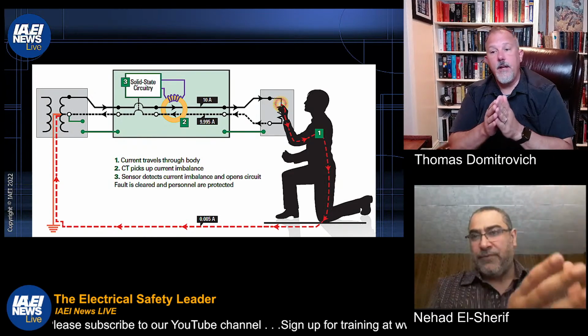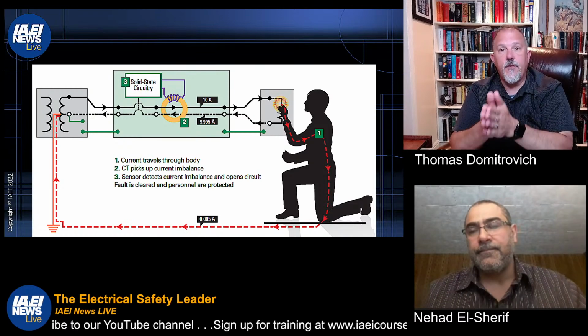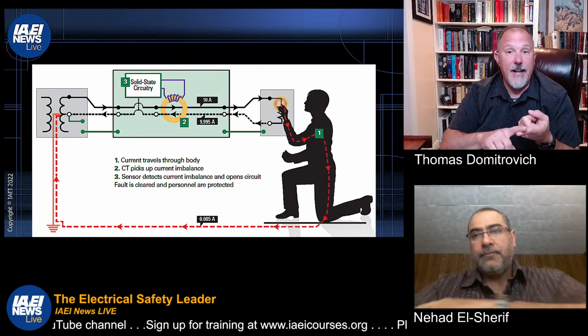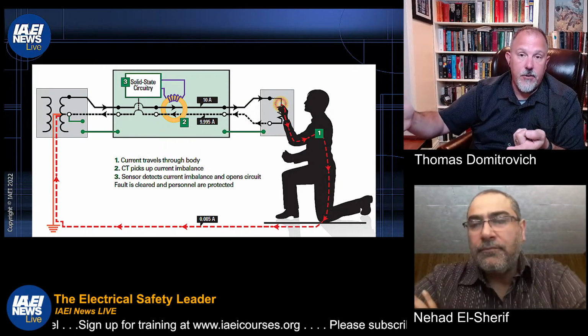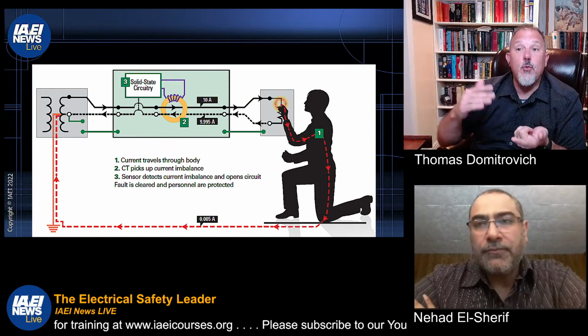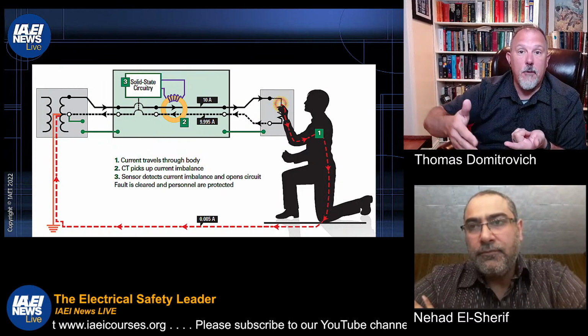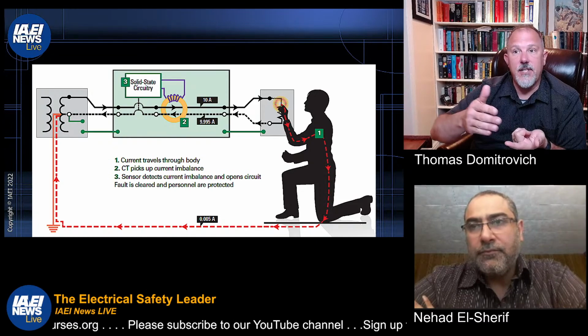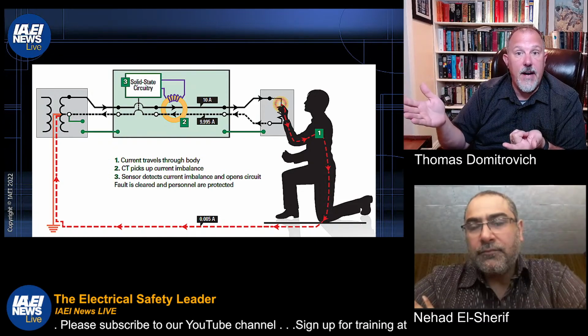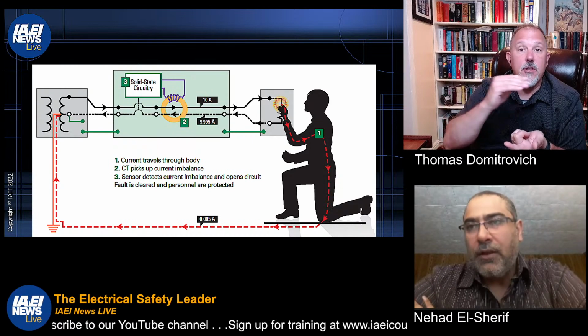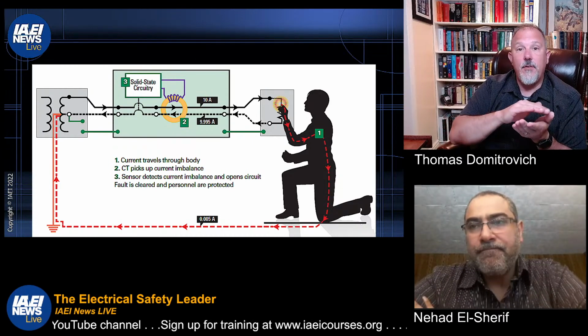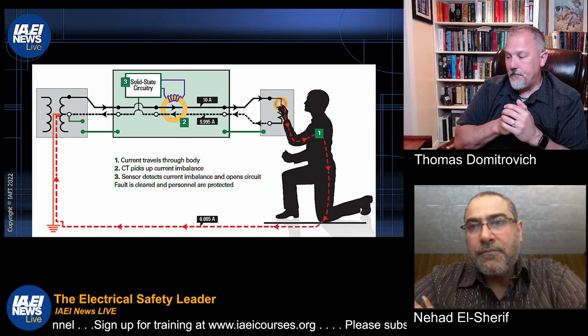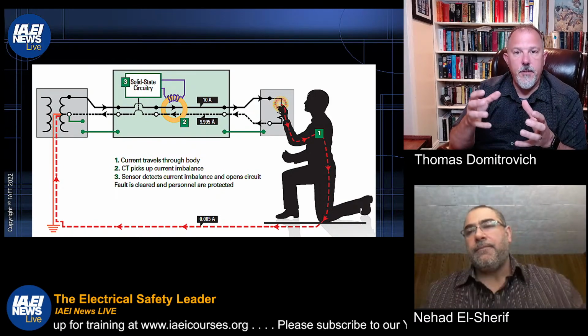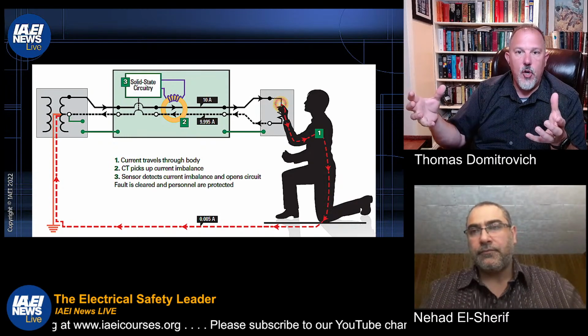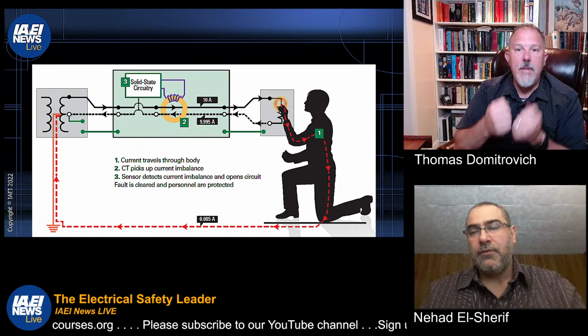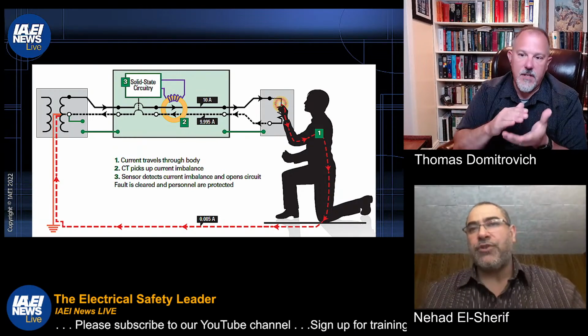So, for equipment protection, for everybody's benefit out there, 230.95 in the National Electrical Code sets a maximum threshold of 1200 amps for ground fault protection of equipment. In addition, you'll see GFPE over in marinas in Article 555 at 100 milliamps, and now we reference 30 milliamps as well. So when you think of ground fault protection of equipment, you're thinking about amps. When you think about GFCI, you're thinking about milliamps. So it's big amps versus little amps.